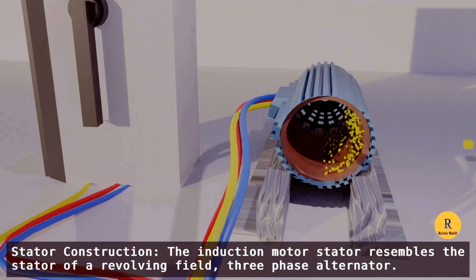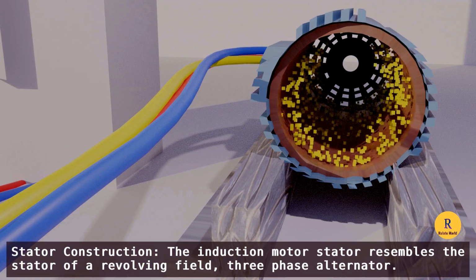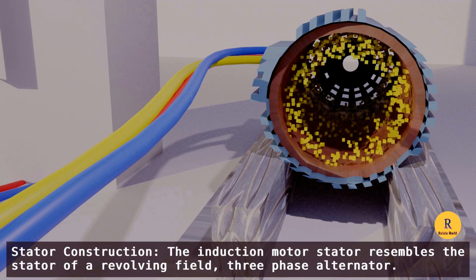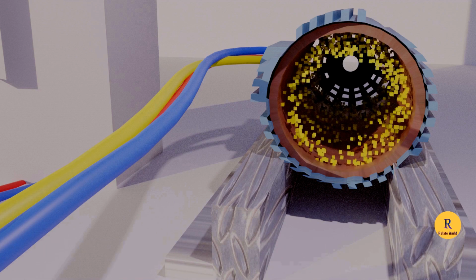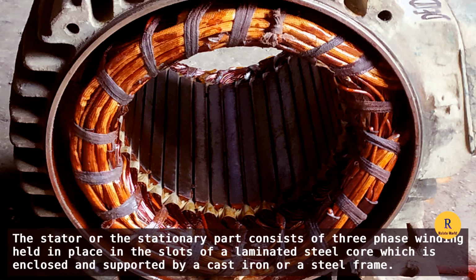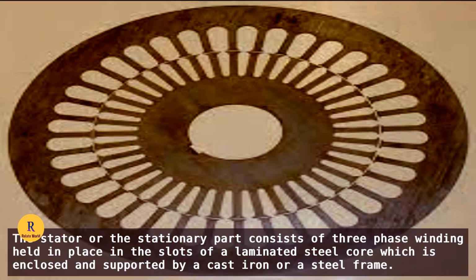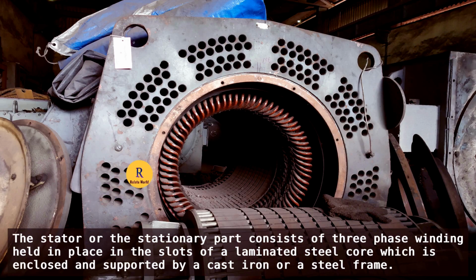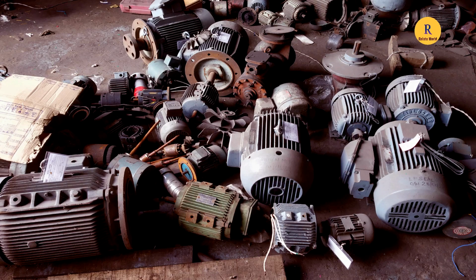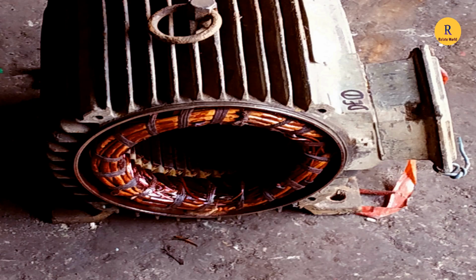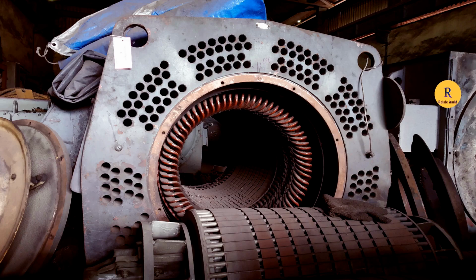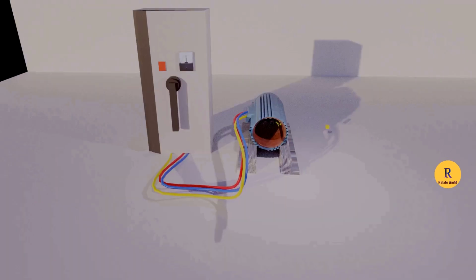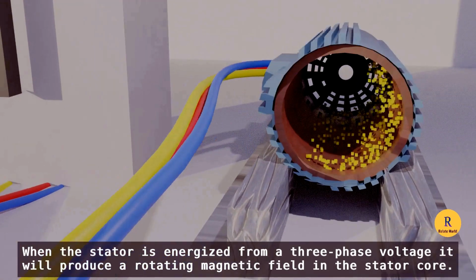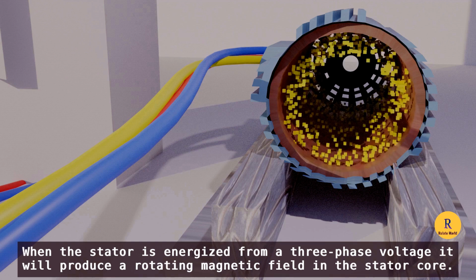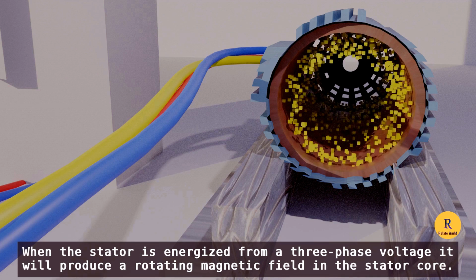Stator construction. The induction motor stator resembles the stator of a revolving field three-phase alternator. The stator part consists of three-phase winding held in place in slots of a laminated steel core, which is enclosed and supported by a cast iron or steel frame, the frame of the motor. When the stator is energized from a three-phase voltage, it produces a rotating magnetic field in the stator core.